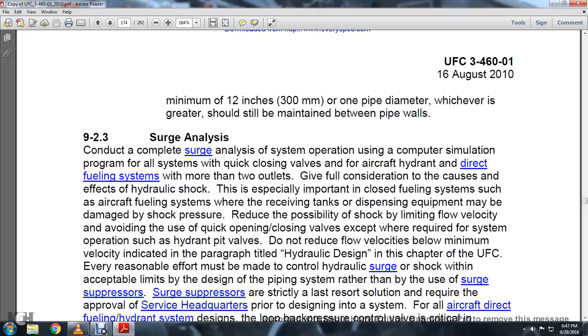Conduct a complete surge analysis of the system operation using a computer simulation program. For all systems with quick closing valves, such as aircraft hydrant and direct fueling systems with more than 2 outlets, give full consideration to the cause and effect of hydraulic shock. This is especially important for fuel systems, such as an aircraft fueling system, where the receiving tanks or the dispensing equipment may be damaged by shock pressure.